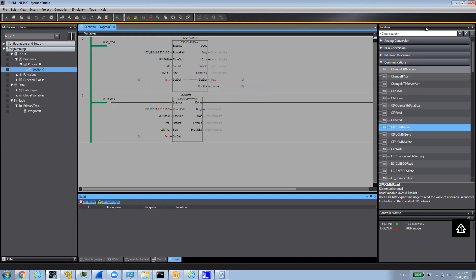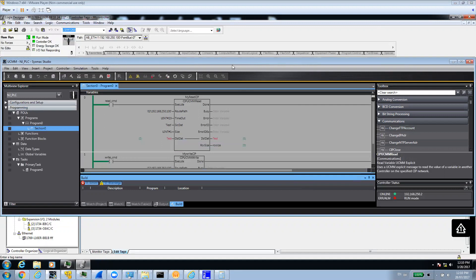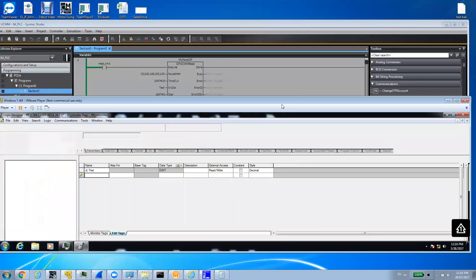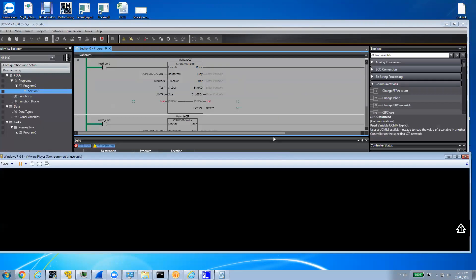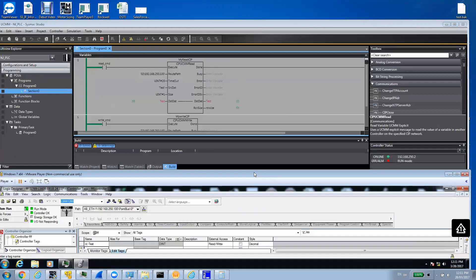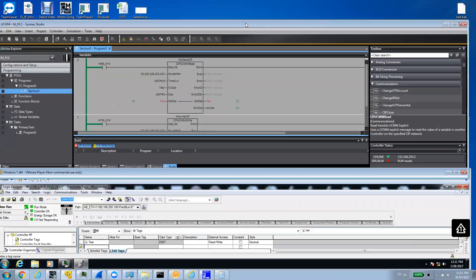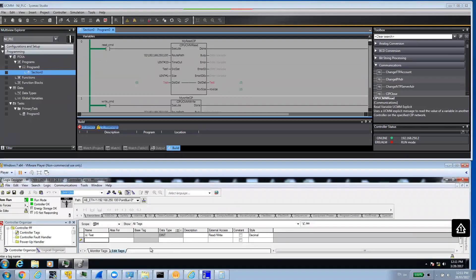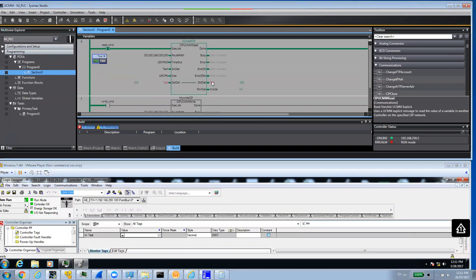We're going to see if we can read from the other PLC. I'm just going to minimize this so we can see it. And do the same thing for this guy as well. All I need is to see the variable. Right now, in test, the value is zero. I'm going to change it to something else so we can see if we are reading it in this PLC. If I get the command true, we can see the command went true. Everything is good. Done. And we're reading the value of 10. And it's 4 bytes because it's a double integer.